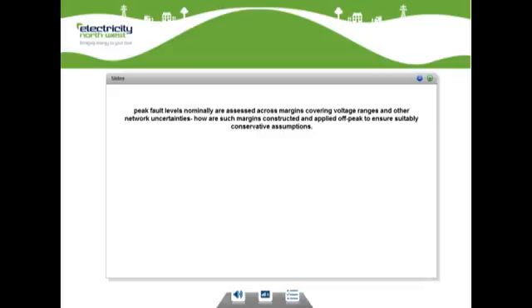So the first question is, peak fault levels normally are assessed across margins covering voltage ranges and other network uncertainties. How are such margins constructed and applied off-peak to ensure suitably conservative assumptions? I think at the moment, as I said, we're just at the start-up of the project, so this sort of question is going to be answered as we progress further down the line. We're working closely with Schneider, who are carrying out some of the fault level work on the network management system. We'll be carrying out fault level load flows, etc.